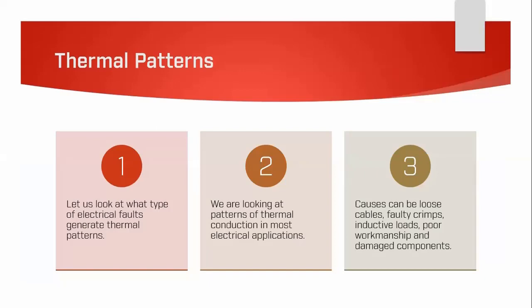The first thing we need to understand is what type of thermal patterns we're looking at. Thermal patterns show areas within electrical installations that might be defective — we can detect high resistance joints, imbalanced phases, faulty crimps, and even poor workmanship and design. Primarily we are looking at patterns of conduction, one example being a thermal gradient — a changing temperature over distance.